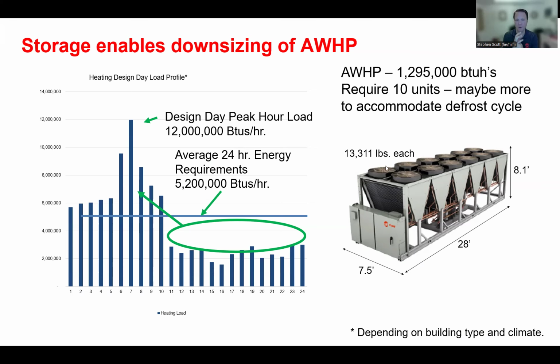So you have to size all of your air source, outdoor heat pumps for that peak instantaneous load. When we're sourcing from water, we end up taking the overall BTUs, downsizing the outdoor units, and putting heaters inside the building to handle the actual BTUs. Rather than sourcing from outdoor ambient air, we're sourcing from those ice tanks and making ice. The green arrow shows that when there's less heat demand during the day, we're melting that ice.